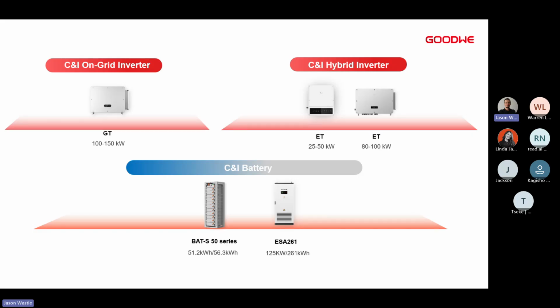Other places where we are seeing a lot of C&I solutions being installed are areas where there is a very stable grid connection. However, there is a high power demand, meaning that we are using a lot of electricity from our national grid, and it's obviously quite expensive. That's where our C&I on-grid inverters come into play. From the 100 to 150 kilowatt inverters, we are seeing a lot of these still being deployed nowadays, and not every solution is necessarily being done just for backup or bad power in the area. We're using it for things like peak shaving, just to curb the cost, as well as to help take some of the tension off the grid during normal everyday operation.